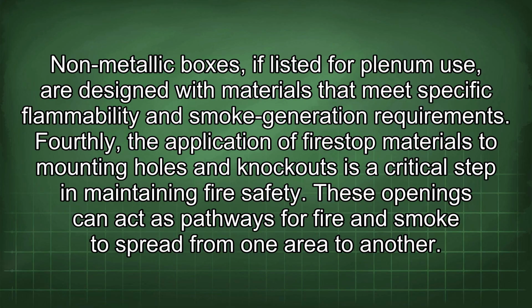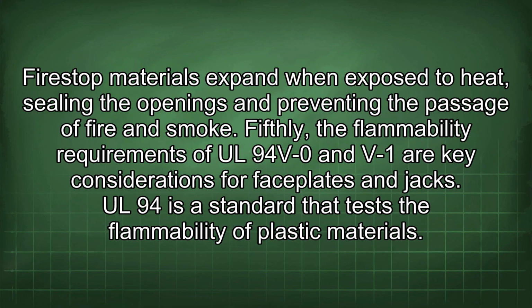Fourthly, the application of Firestop materials to mounting holes and knockouts is a critical step in maintaining fire safety. These openings can act as pathways for fire and smoke to spread from one area to another. Firestop materials expand when exposed to heat, sealing the openings and preventing the passage of fire and smoke.